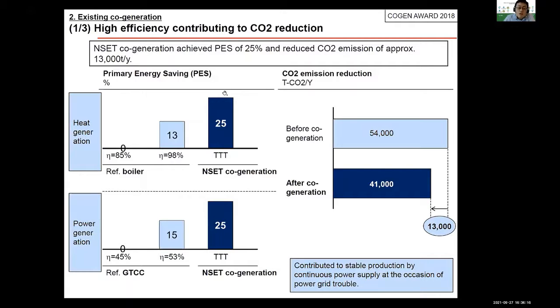Since the cogeneration is highly efficient, we've achieved a high PES of 25%. Primary energy saving, PES, is an indicator used in Thailand to evaluate the efficiency of cogeneration. This PES implies this plant reduced primary energy by 25% compared to a boiler, of which efficiency is 85%, and a gas turbine combined cycle, of which efficiency is 45%. And this plant can contribute more to primary energy saving than a highly efficient boiler or an advanced gas turbine combined cycle plant.